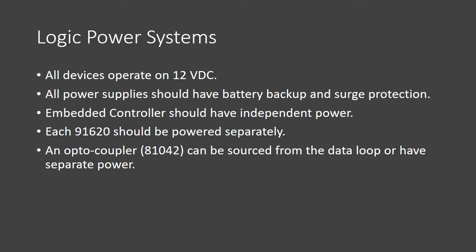Power is an extremely important consideration when talking about these devices. Some commonalities for power considerations for these devices is, first of all, MTI devices are powered via 12 volts DC, and typically a power supply is provided as part of that part, whether it's the embedded controller or 620. All power supplies provided for the MTI system should have battery backup that is sufficient for that device, and surge protection. It's utterly important, especially on a control system, that those devices be backed up.